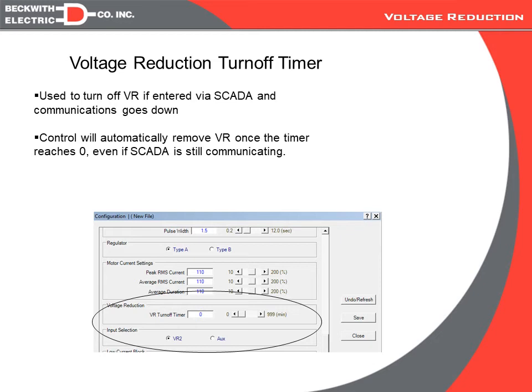Also, we can see under the input selection screen that second VR reduction input can be used for hardware reduction or can be used as an auxiliary DNP input. So we have cases where customers on bus regulators have a temperature alarm contact that they want to bring back into SCADA. Well, if you're using the voltage reduction via communications, you don't need the hardware inputs, and so this is a way of freeing up one of those hardware inputs so that it's not tied to voltage reduction.